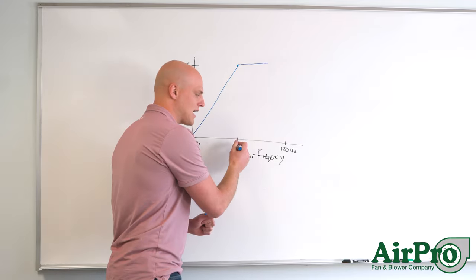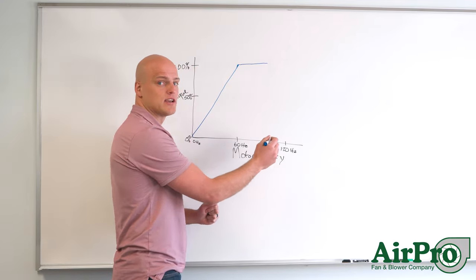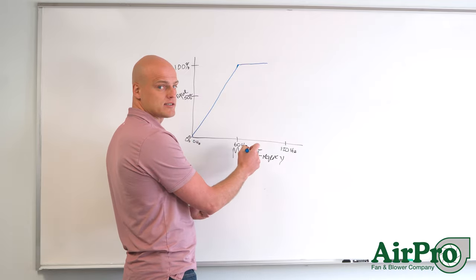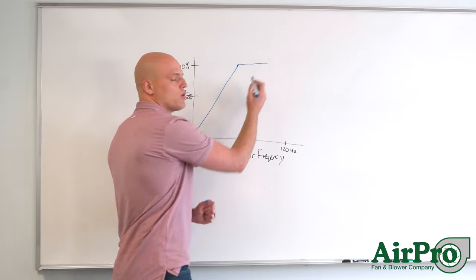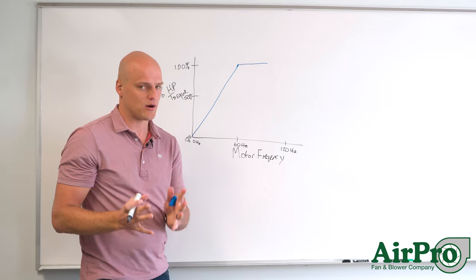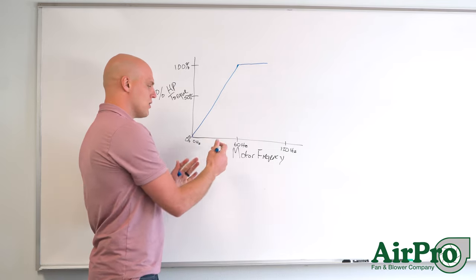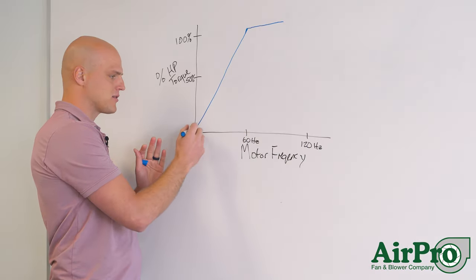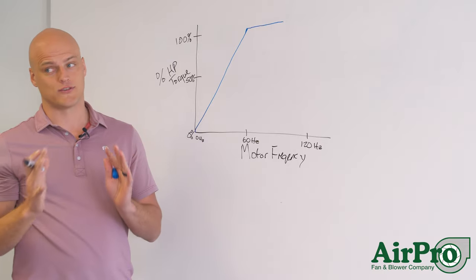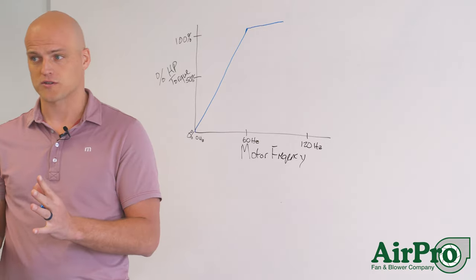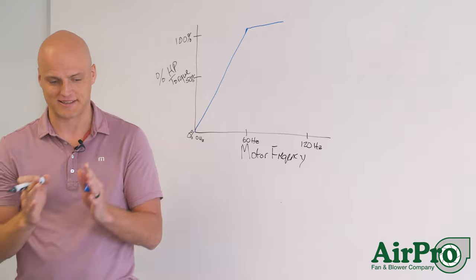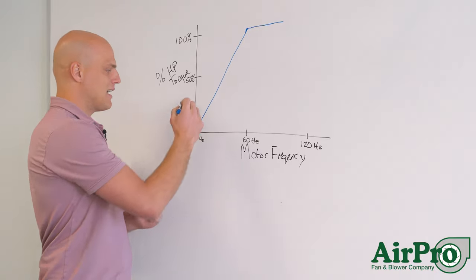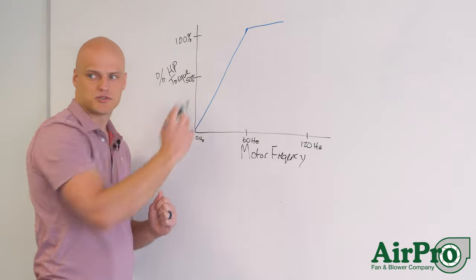As high as the motor is able to run in frequency past 60 hertz you have the full nameplate horsepower available. But notice at less than 60 hertz from 0 to 60 you don't have the full motor horsepower available that's on the nameplate. And it is proportional to your speed.